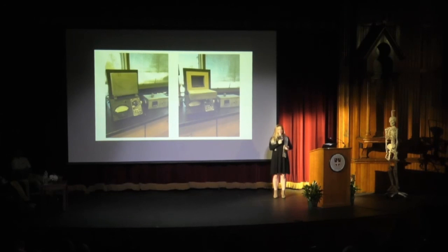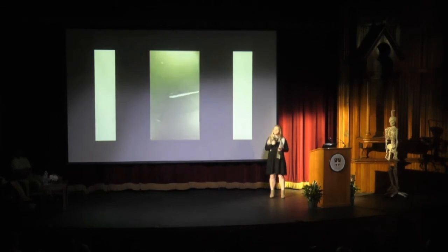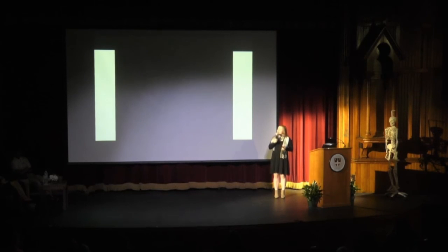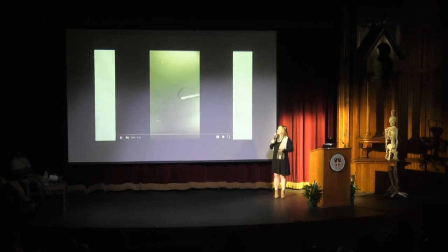Simple enough, right? I know it doesn't look like much, but the oven in these pictures can actually heat up to around 2,000 degrees Fahrenheit. So what you will see in this video is one of the nitinol springs that we shaped in the small box furnace in the lab. You will see the spring being pushed out of a straight cannula and then recoiling back into its original position. So what this shows is basically the mechanism by which the spring would be inserted into the intervertebral space.